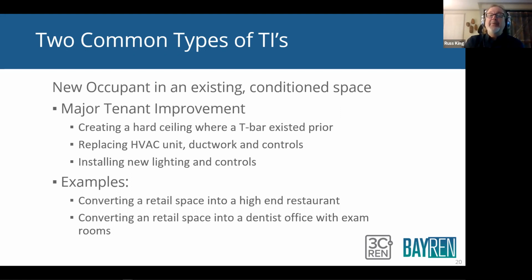restaurants. Restaurants always are a lot of work. So adding a restaurant to where there wasn't one before is a big deal. You're going to put a hard ceiling in where there used to be a T-bar. Maybe you're putting in a whole new different HVAC system. You're having to put in a bigger system because you've got more loads. Maybe you're adding a huge kitchen hood and changing the ventilation system. You've got all different kinds of lighting, and controls are all going to be different for a restaurant than they were, say, for a retail space, okay?